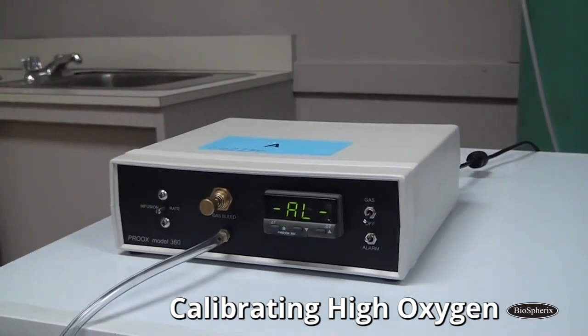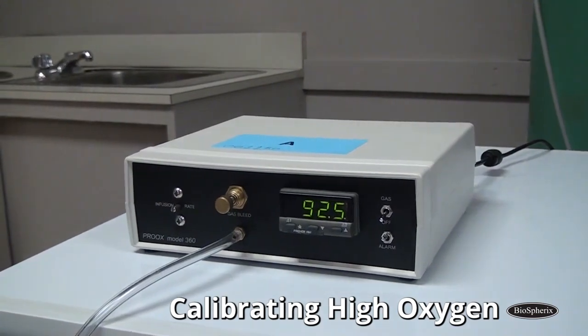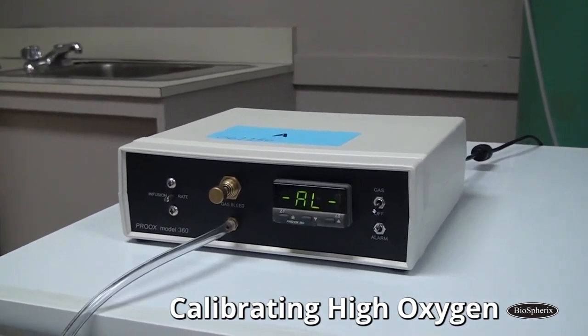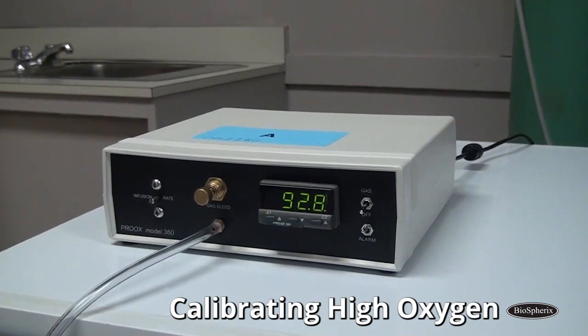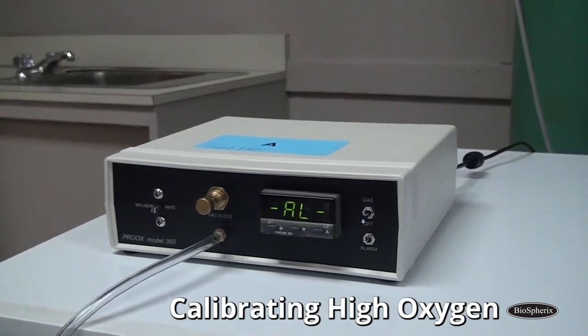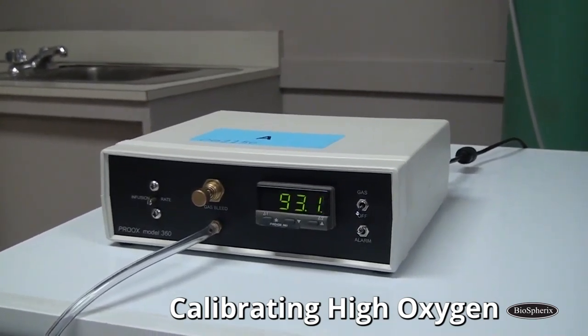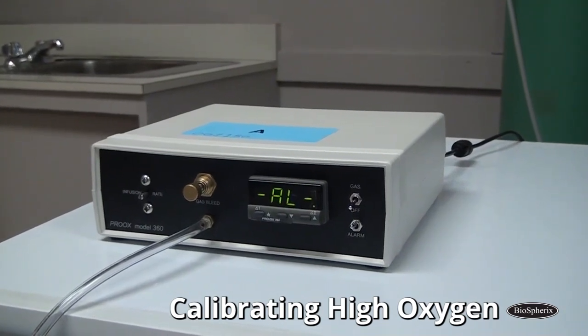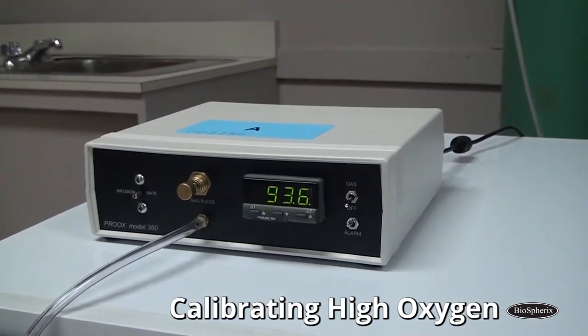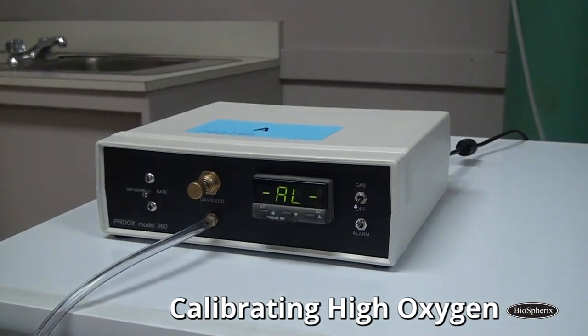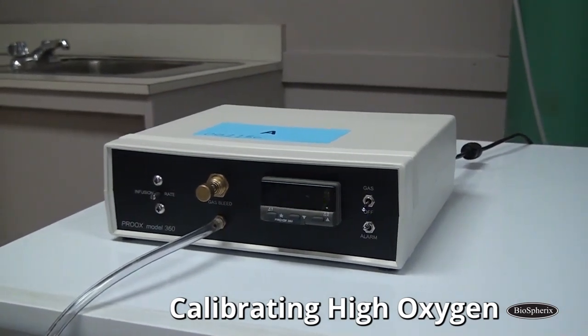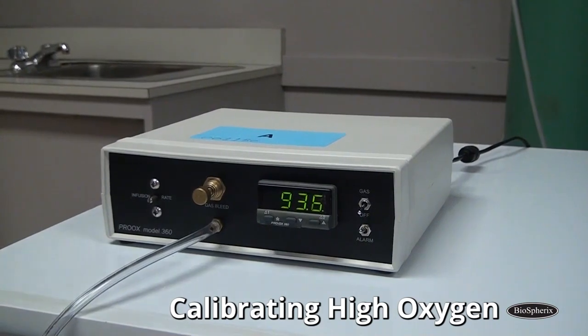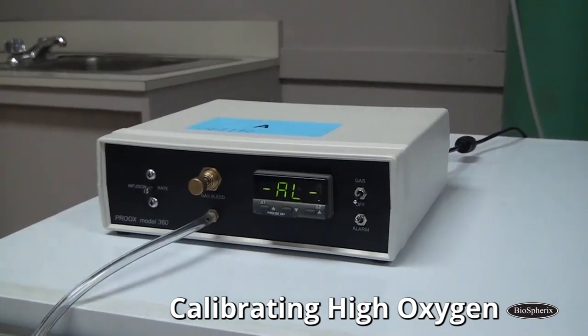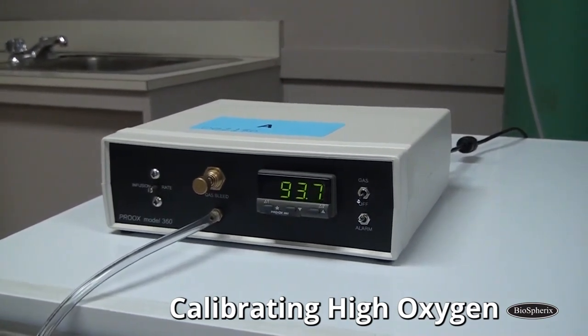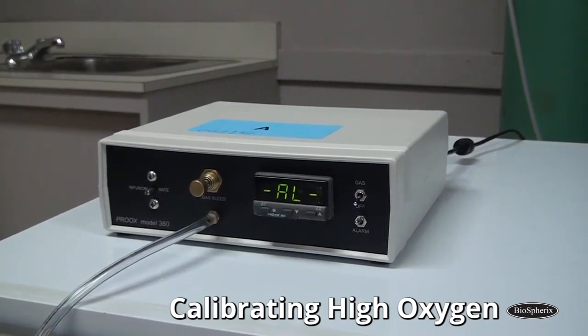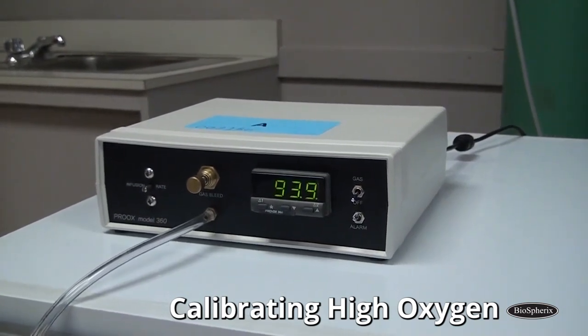When you're using pure oxygen, it's always a little less accurate for a couple reasons. Number one, room air for your 0, 20.8, that's a little less accurate than if you were to use nitrogen for your 0, because room air can fluctuate a little bit, that percentage. Also, the sensors really only read 99.9, and at that very, very top end, it's real tough for them to be super accurate. So we get as close as we can.